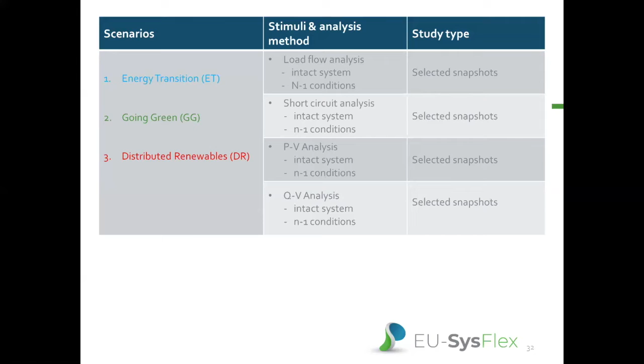On behalf of PSE, I would like to present the key results and conclusions regarding the analysis of the power system model in Central Europe. Regarding steady state voltage control analysis, 4 types of calculations have been carried out, including load flow, PV and QV analysis, focused on identifying steady state reactive power scarcity, and short circuit analysis, focused on system strength.